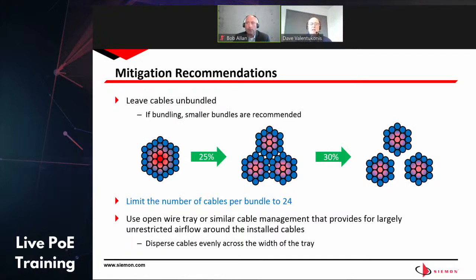What they found in the studies is if you take those bundles and reduce them—for example, 90 cables—if you take those 90 cables and reduce them into three groups of 30 cables, it reduces the heat on the center cables by 25%. Further, if you add an inch of separation, it reduces the heat on those central cables another 30%. So simply moving away from those big bundles to more managed bundles is a good thing.